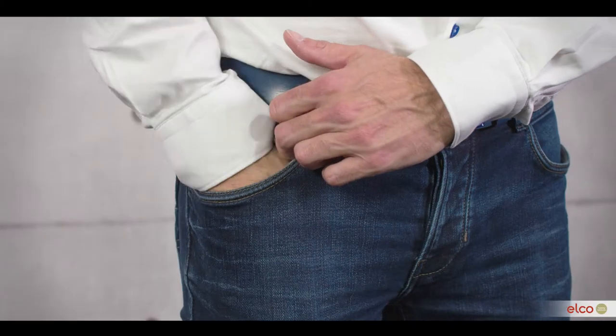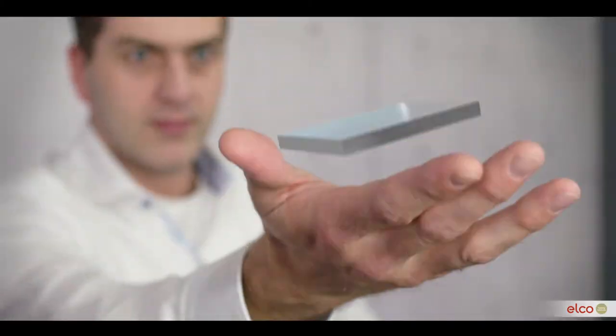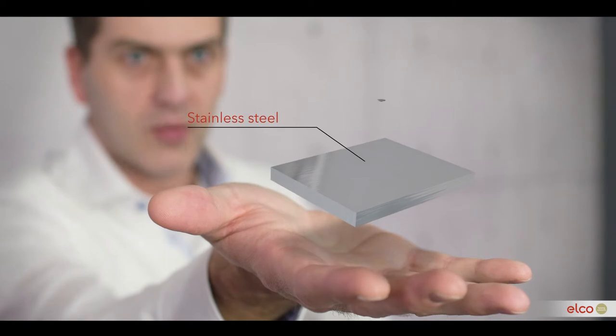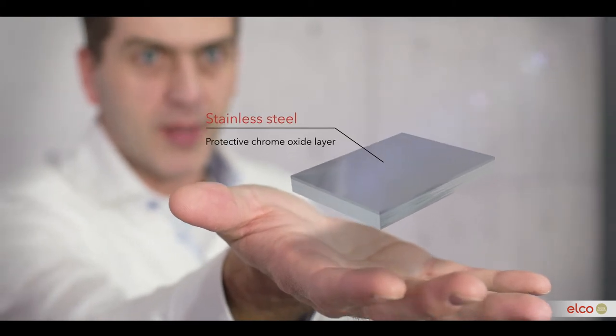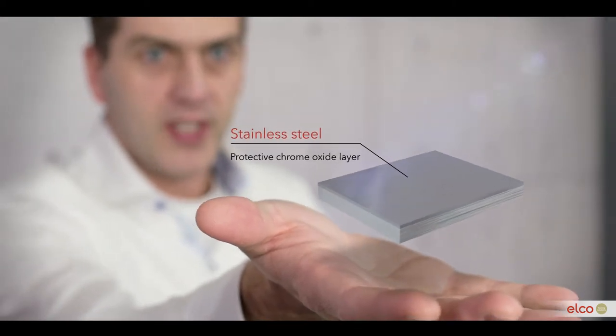Heat exchangers made from stainless steel have a protective chrome oxide layer, thanks to a chrome percentage of more than 10%. This chrome oxide layer is hardly affected by the acidic condensate, so the heat exchanger's surface remains smooth and clean.